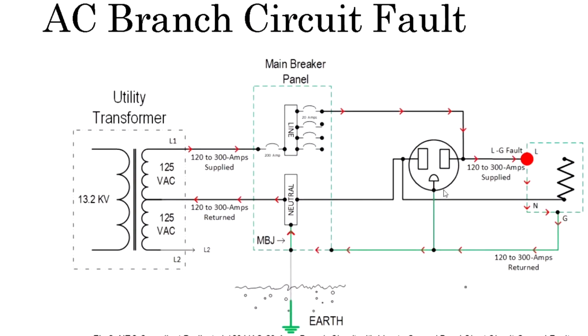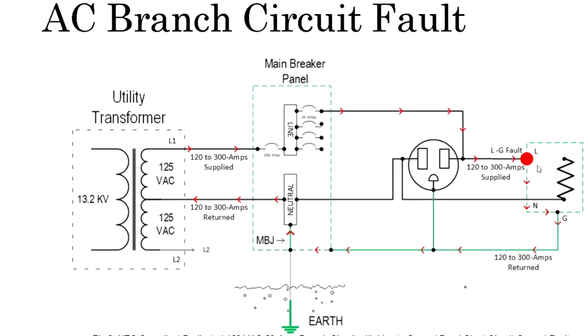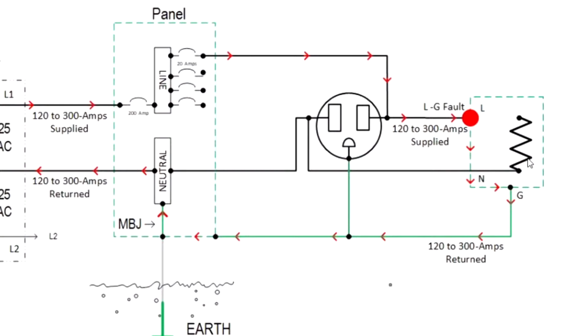Think about what's going on here. We've got 120 volts applied between right here on the line and right here on the ground and neutral. Each one of these conductors is the same size, 14 gauge, and they're the same length. Right here at this chassis, we've got a perfect voltage divider. So under that fault condition, for half a cycle there'll be about 60 volts on this chassis. It's limiting the potential to tolerable limits so you don't get electrocuted. And it should operate, inducing at least 120 amps, within about half a cycle, 120th of a second.